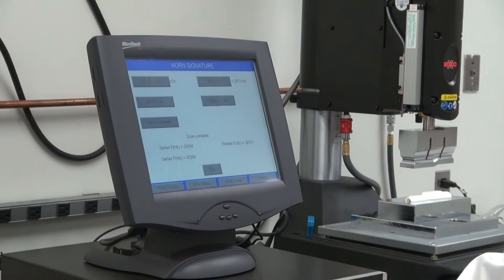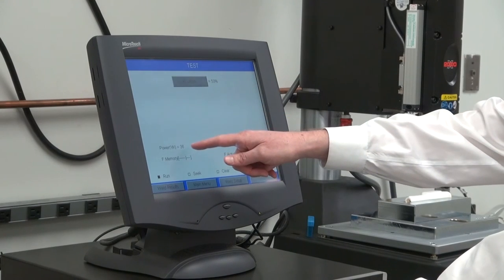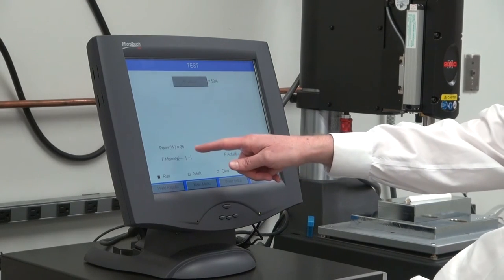From this point, I can do a test of the horn. If I press the test button, I'll see the power here. This is 50% amplitude I'm running at, 36 watts, and the frequency that it's running, 29.758 kilohertz. 34 watts is about right for the power for this. That's a good frequency right here. This horn is good. I'm ready to go.